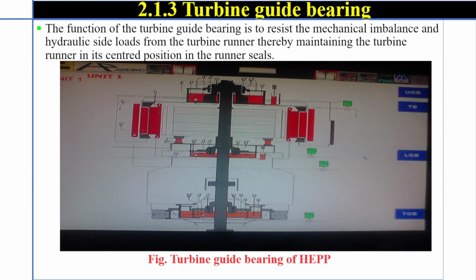2.1.3 Turbine guide bearing. The function of the turbine guide bearing is to resist the mechanical imbalance and hydraulic side loads from the turbine runner, thereby maintaining the turbine runner in its centered position in the runner seals. As you can see, these are the lower guide bearing, upper guide bearing, and turbine guide bearing.